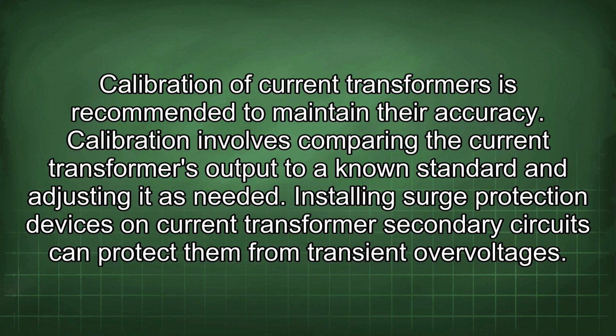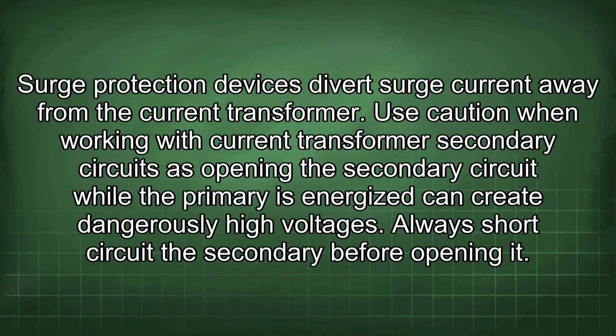Calibration involves comparing the current transformer's output to a known standard and adjusting it as needed. Installing surge protection devices on current transformer secondary circuits can protect them from transient overvoltages. Surge protection devices divert surge current away from the current transformer. Use caution when working with current transformer secondary circuits, as opening the secondary circuit while the primary is energized can create dangerously high voltages. Always short circuit the secondary before opening it.